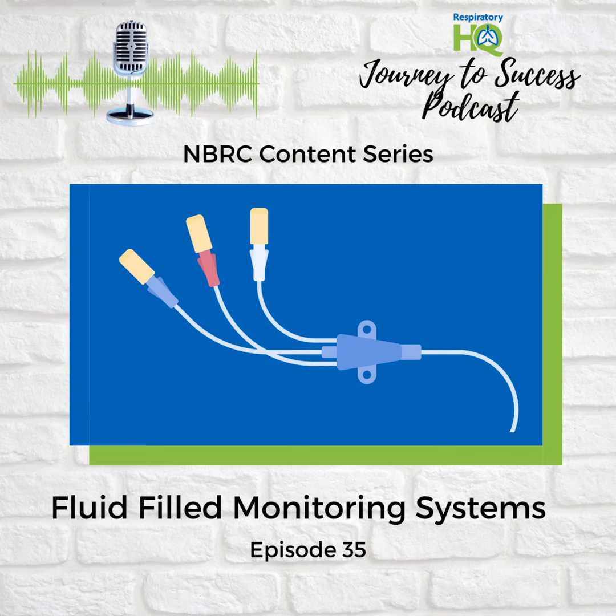Inertia. Inertia, like from physics class. Exactly. Inertia is the tendency of an object to resist changes in motion. Right. So in this case, the fluid in the monitoring system can't keep up perfectly with the rapid pressure changes caused by the heartbeat. Oh, I see. It's kind of like trying to measure a moving target, but the fluid lags a bit behind. And that can mess up the readings. It can lead to inaccuracies, yeah.